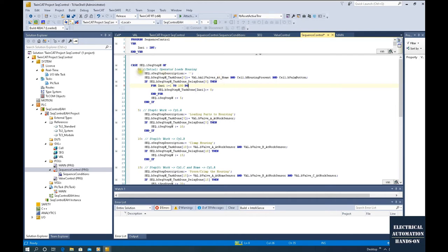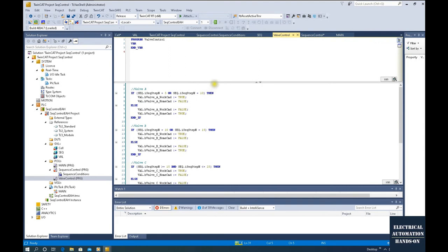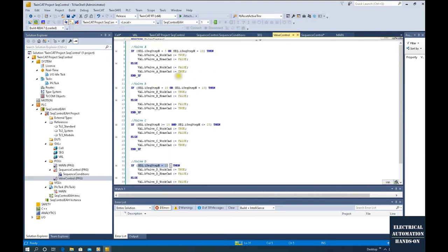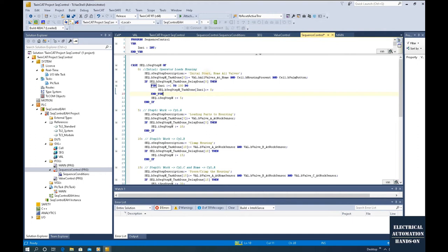And at this step 0, this is the initial start. And meantime, it's home all valves. And when this step is at 0, if we review these conditions, basically those logic will control the valves to go home. This allows when the sequence is at 0, basically all the commands to control the valves, they go home. And if all the valves are at home position, we start from the beginning and we check the housing present. Once they are all good, so once we push this button, turn on, this sequence will move forward. Okay, till here, basically we finish these two main parts.